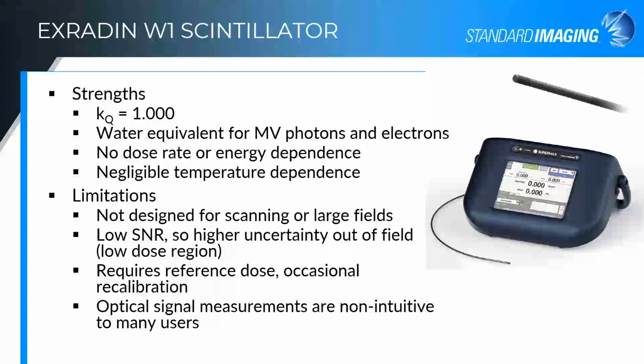As I described for scintillators, it's not a device that you can send in for calibration. You have to give it a cross calibration with a reference dose and an occasional recalibration as the plastics degrade with dose. The other limitation is that there's a bit of a learning curve to this, just because optical signal measurements are not intuitive to some users. Troubleshooting why my measurement doesn't match what I think it maybe should be becomes simpler as you get used to the detector, as you get used to using an optical fiber and handling an optical fiber and interpreting data from that. But it is a little bit of a learning curve if all you've ever used is ion chambers and diodes.